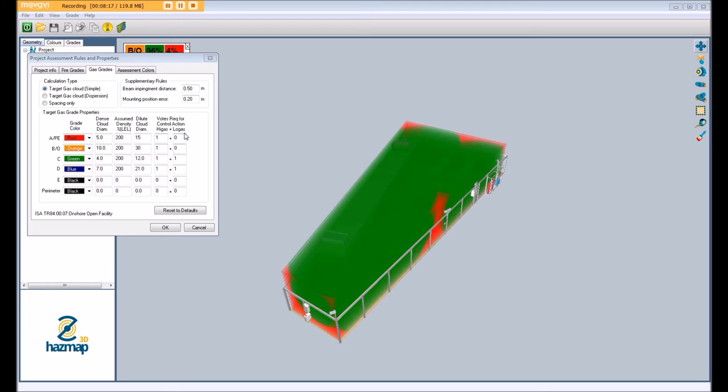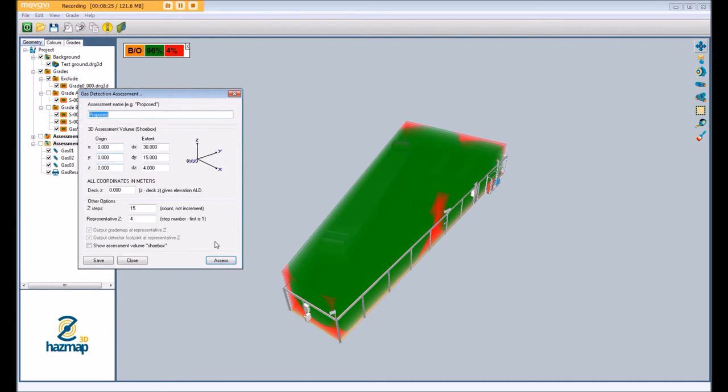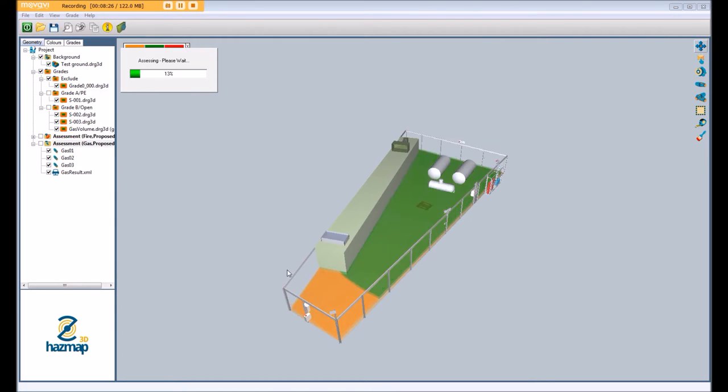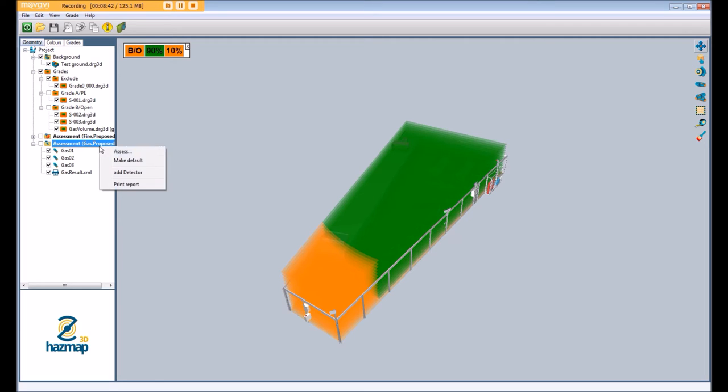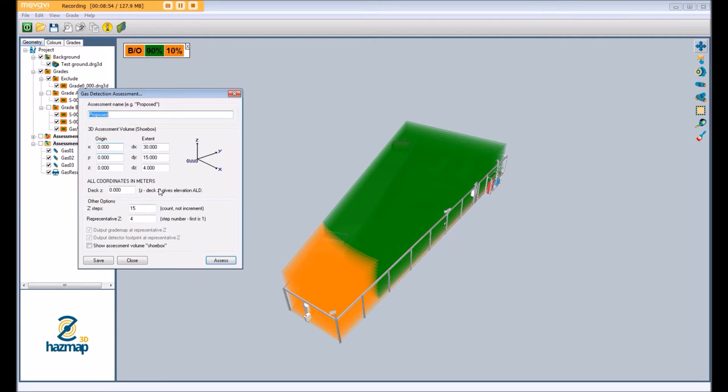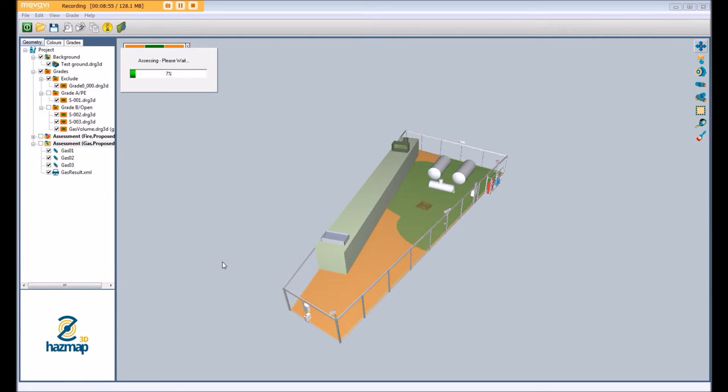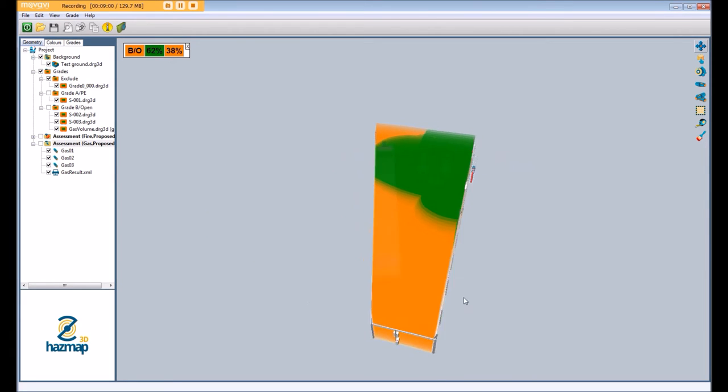You can see that in this assessment when we change our voting requirements to one high gas and one low gas and rerun the assessment. As we saw previously you start to get that incorporation of the fact that you could have a gas cloud of the given diameter which will intersect with one detector at its low gas alarm set point but it wouldn't get high enough to actually set a second detector off at its high gas set point. And obviously this changes again when we change the detector set points and the voting logic. So if we make this no low gas but two high gas before you get an executive action, this is going to change the assessment once more and obviously we get a far more conservative view of the coverage in this instance.